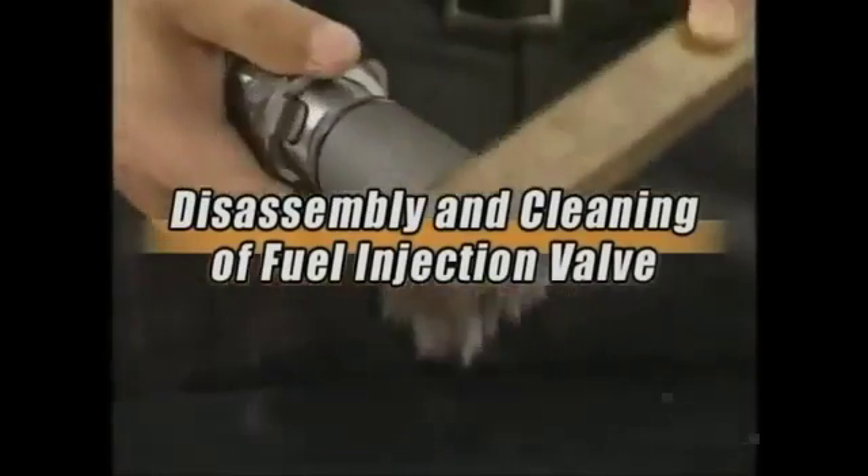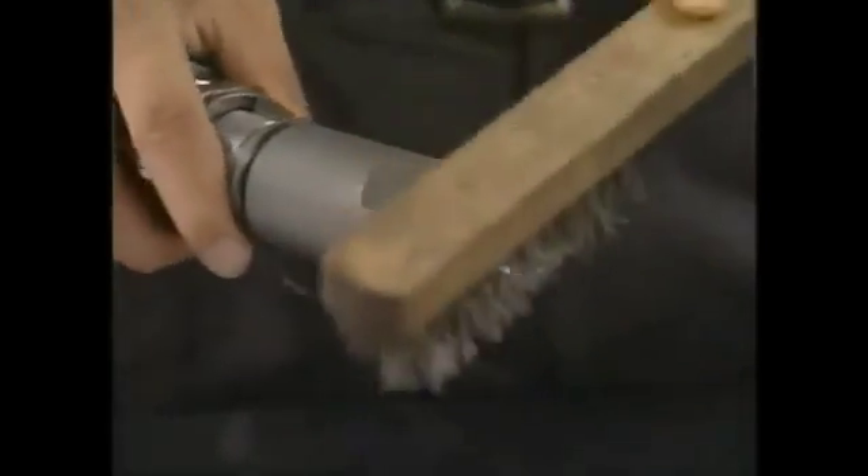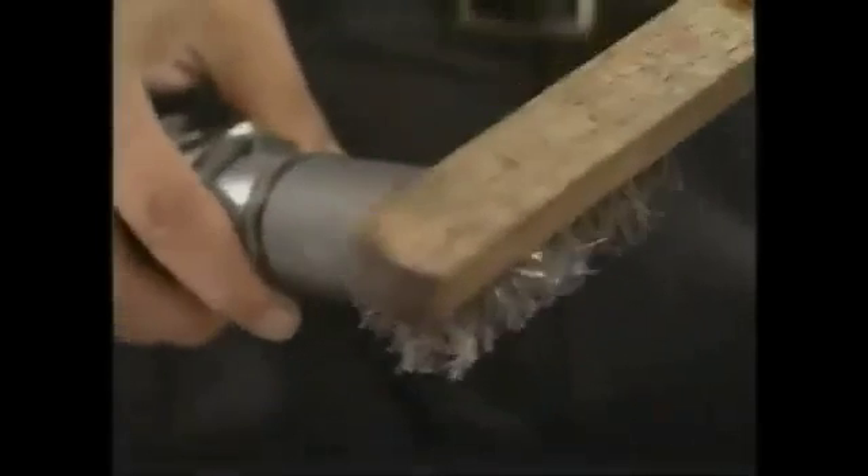Firstly, clean the carbon deposited on the exterior portion of the nozzle. If the amount of carbon deposit is large, remove the extraneous matter by soaking the nozzle in the carbon remover or in the undiluted solution of cresol. Proceed to the disassembly after eliminating the carbon.